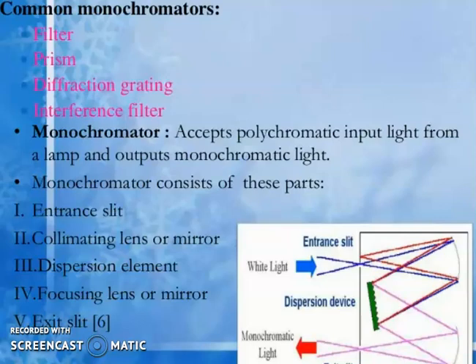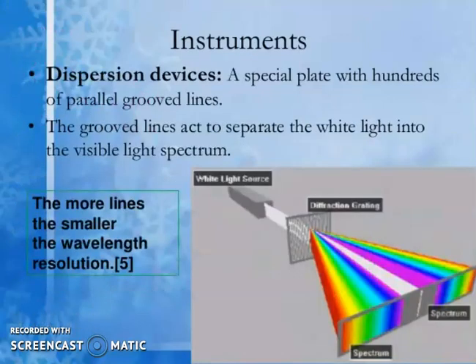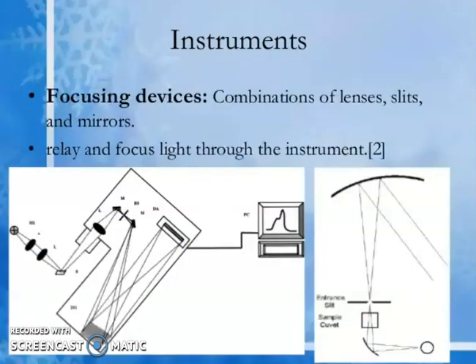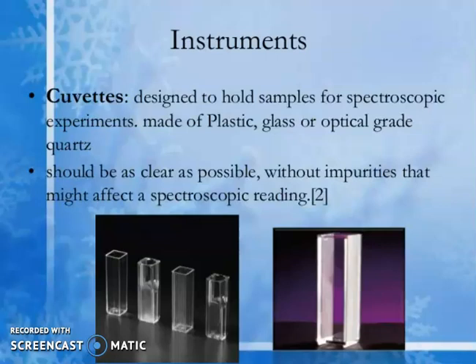The monochromator accepts polychromatic input light from a lamp and outputs monochromatic light. It consists of a collimating lens or mirror, dispersion elements, focusing lens or mirror, and exit slits. The diffraction grating is a special plate with hundreds of parallel grooved lines that separate white light into the visible spectrum — the more lines, the smaller the wavelength resolution. The focusing device is a combination of lenses, slits, and mirrors that relay and focus light through the instrument. Cuvettes designed to hold a sample for spectroscopic measurement are made of plastic, glass, or optical-grade quartz and should be clear.